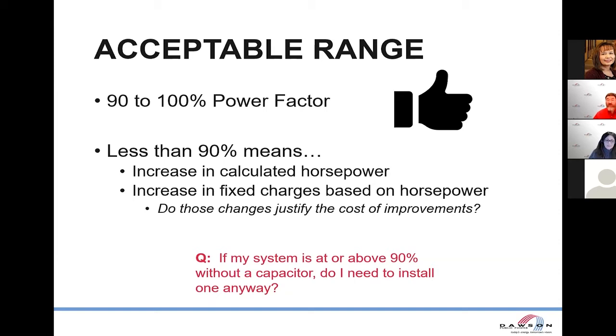So if your system is above 90% without a capacitor, do you need to install one anyway? The answer is no. If you're above 90%, you're good enough. Whether that's because you have a VFD, because you have an incredibly efficient motor, for whatever reason, if you're above 90%, don't worry about it. You're not going to get an additional charge. So no longer will we be out looking for that capacitor, right? If you're above 90%, we don't care how you got there, just that you're there.